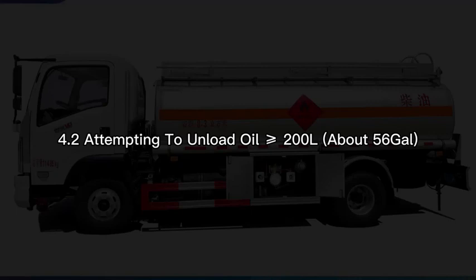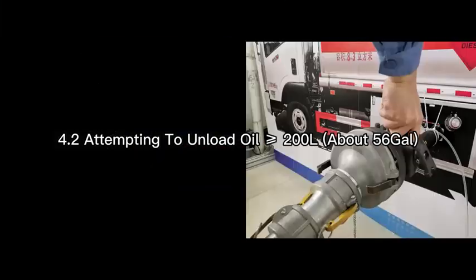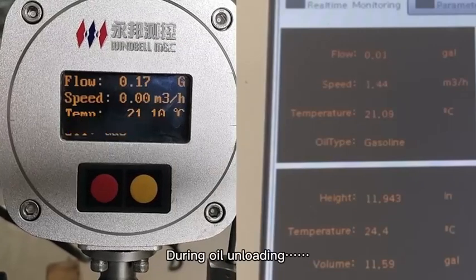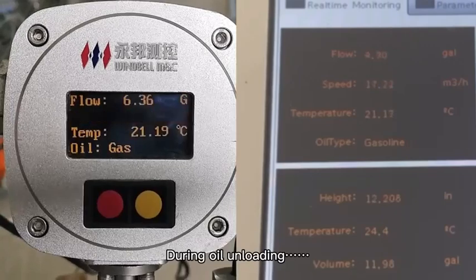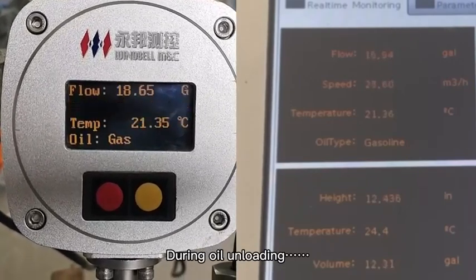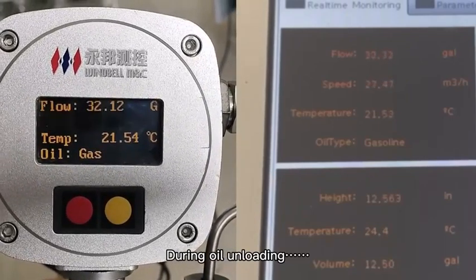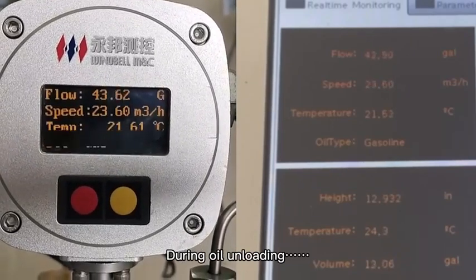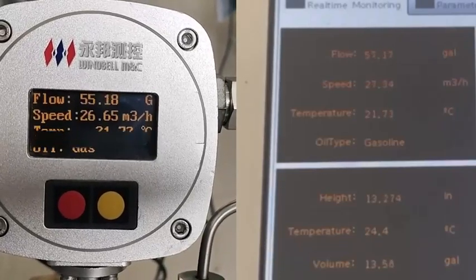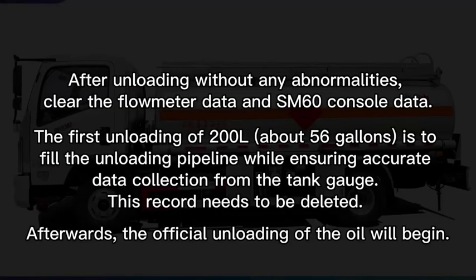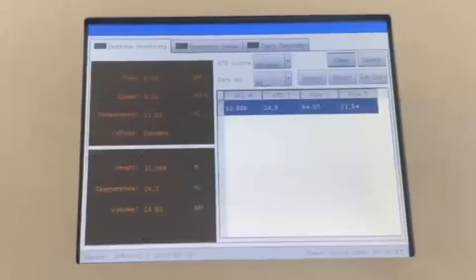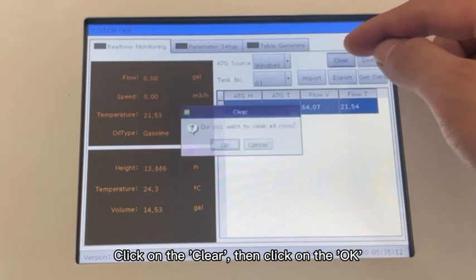2. Attempt to unload oil greater than or equal to 200 liters, about 56 gallons. Simultaneously open the oil unloading port. During oil unloading, after unloading without any abnormalities, clear the flow meter data and SM60 console data. The first unloading of 200 liters, about 56 gal, is to fill the unloading pipeline while ensuring accurate data collection from the tank gauge. This record needs to be deleted. Afterwards, the official unloading of the oil will begin. Click on Clear, then click on OK.